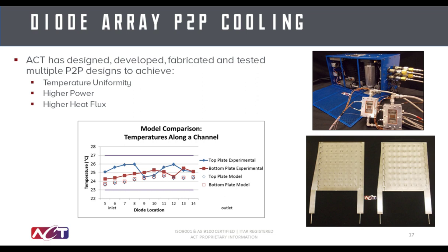ACT has developed two-phase cold plates for this application. Shown here is a plot of a cold plate that incorporates 1.8 square feet of laser diode arrays with a requirement to maintain the diodes within plus or minus 3 degrees C across the entire array. ACT developed the cold plate and the supporting two-phase system to be able to achieve these targets, as shown on the plot. Also of note here is the accuracy of ACT's modeling approach as compared to the actual experimental data. You can see that good agreement was achieved.